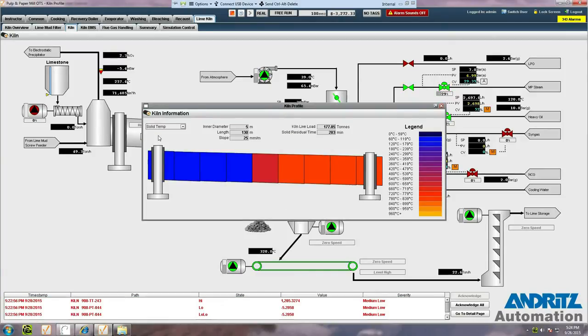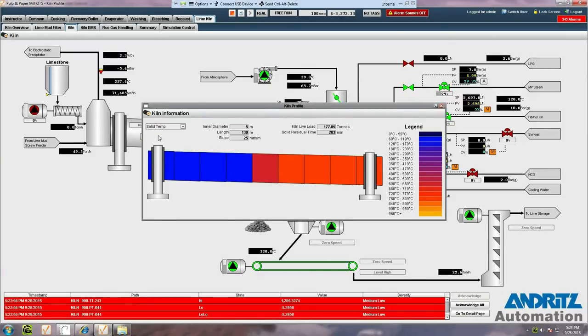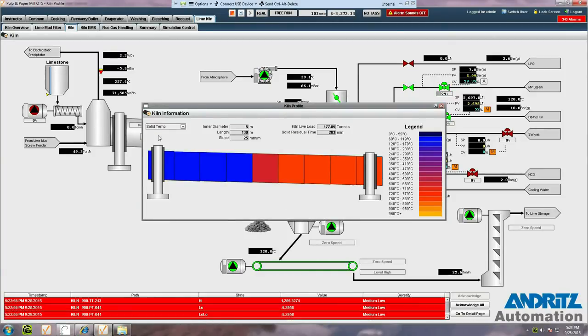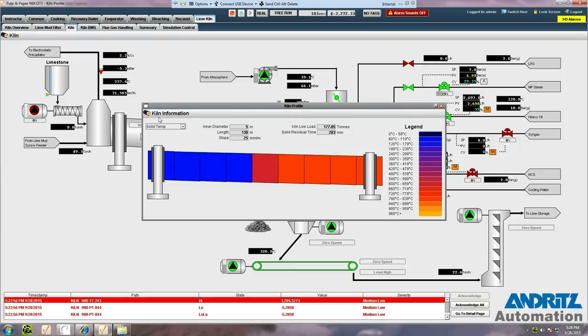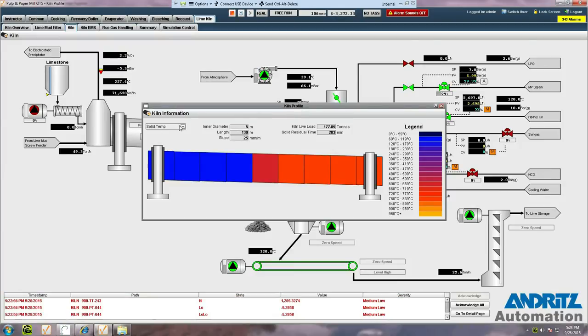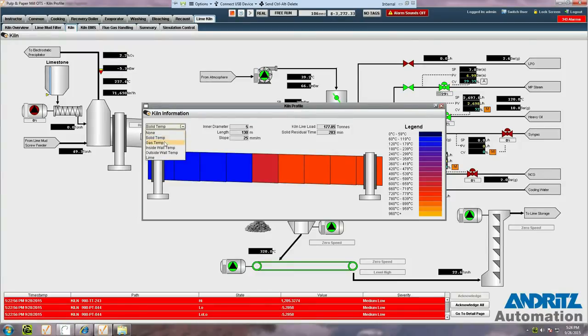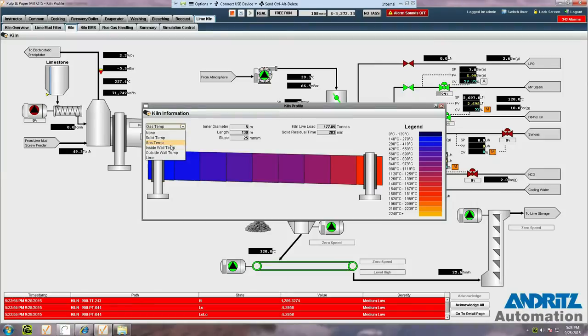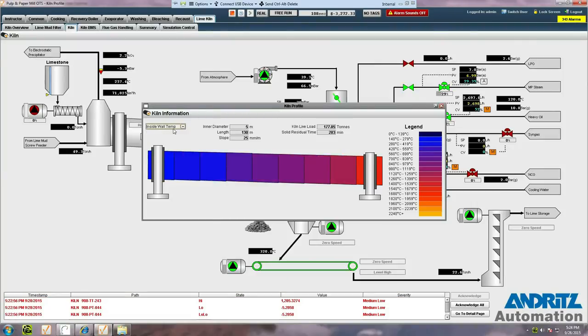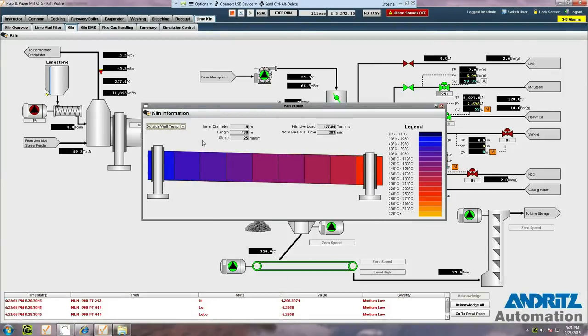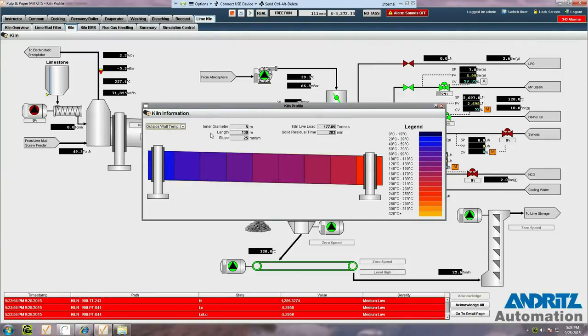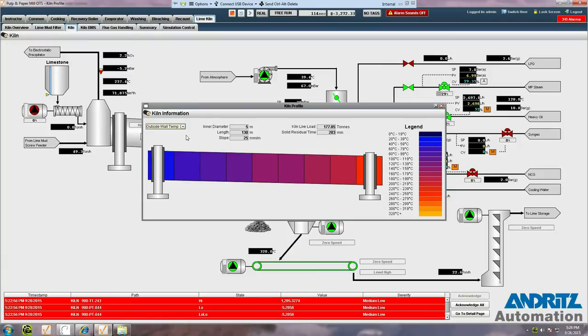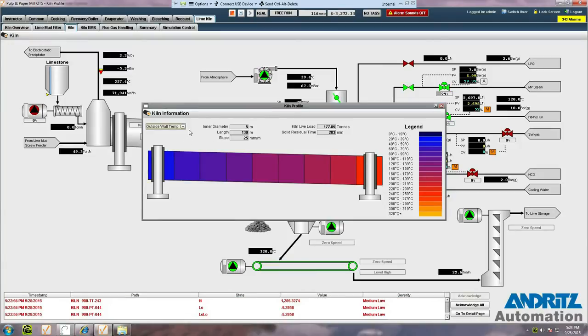Here, we can see an internal profile of what's actually going on inside the kiln. We can view a variety of temperatures for the solids, the gas, the inside wall, and the outside wall temperatures. These are being updated in real-time based on information that's provided from the model.